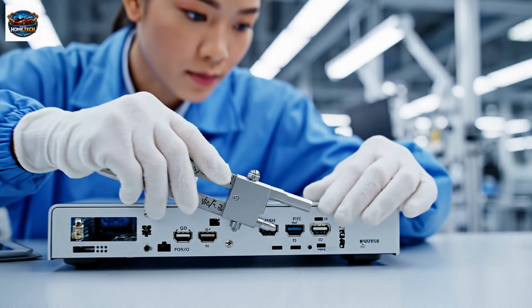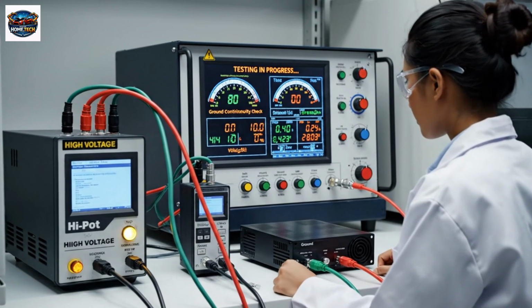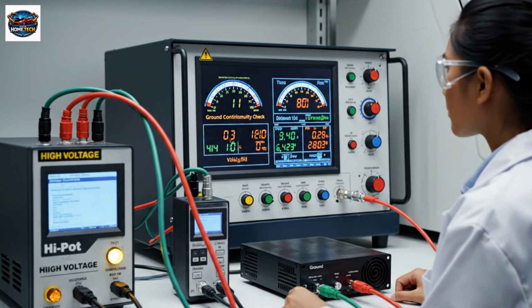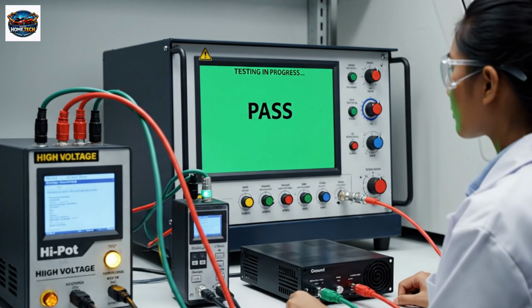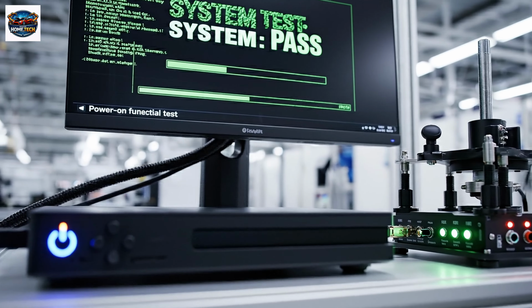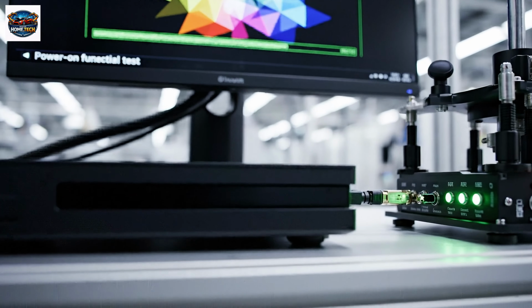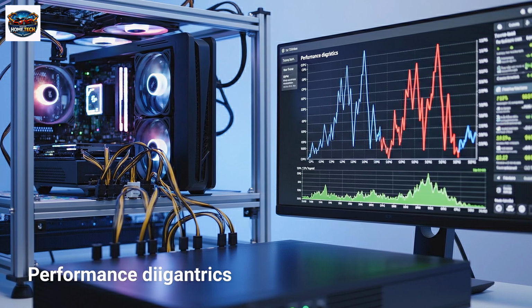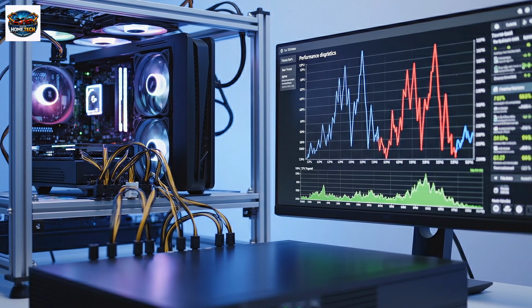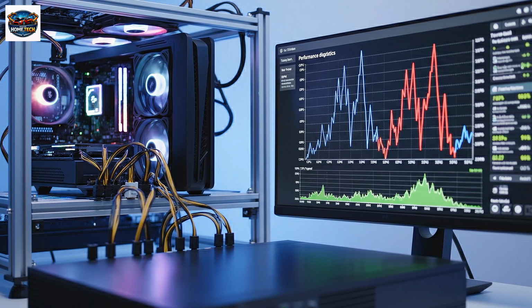Each unit is registered as it enters end-of-line testing. Electrical safety tests verify insulation and grounding compliance. The console is powered on to confirm core system functionality. Performance checks ensure the system operates within design limits. External interfaces are verified for full user functionality.